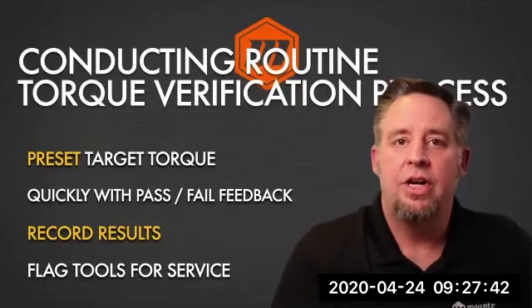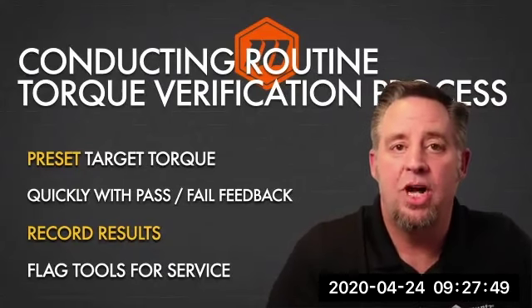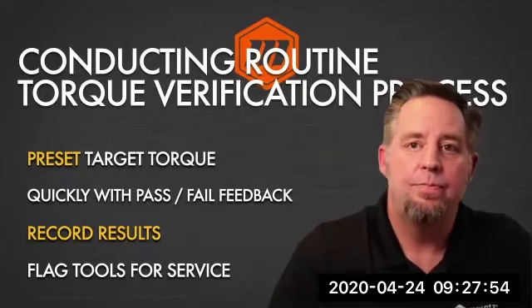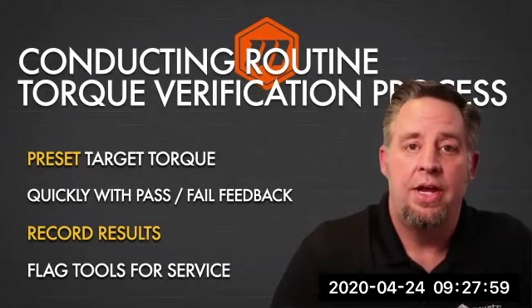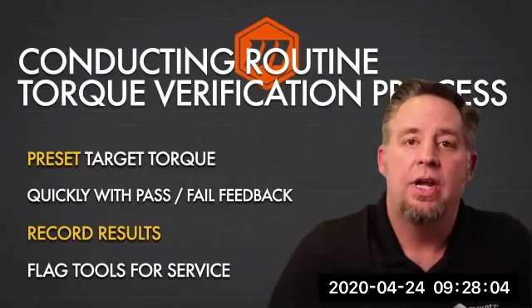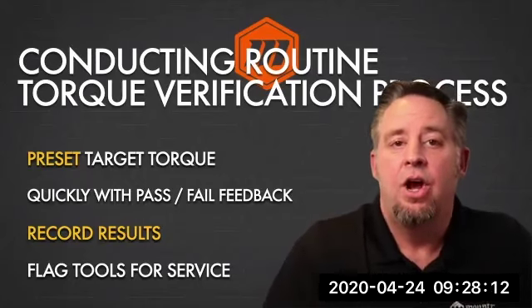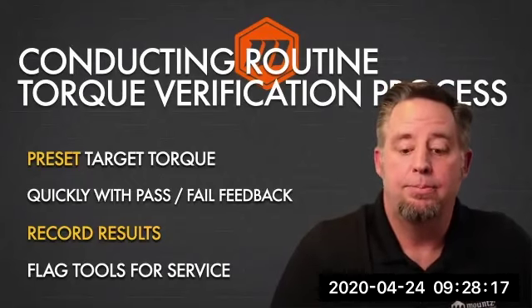So now, if you're conducting a routine torque verification, some things that might help the process would be using an analyzer that would have a preset torque value target that you can either enter in, or you can have it visually pull up on the screen to give you a quick pass and fail feedback feature. It's going to record the results for you, and then also you could flag that tool for service at that particular time.